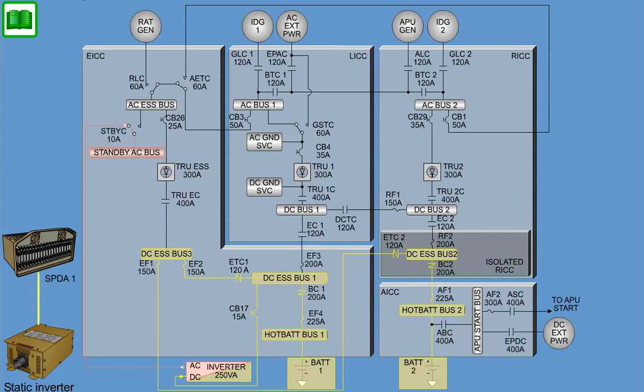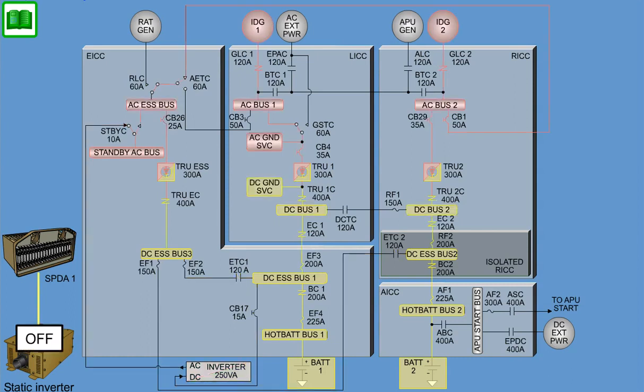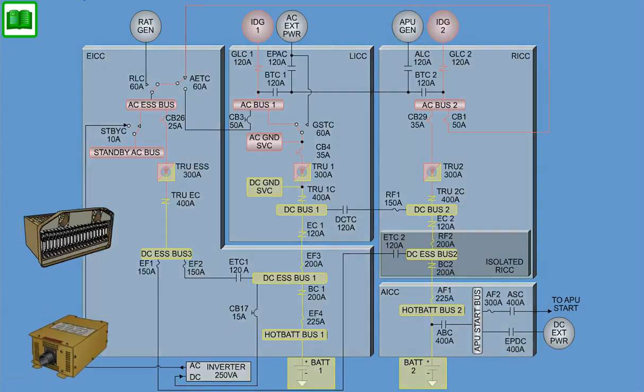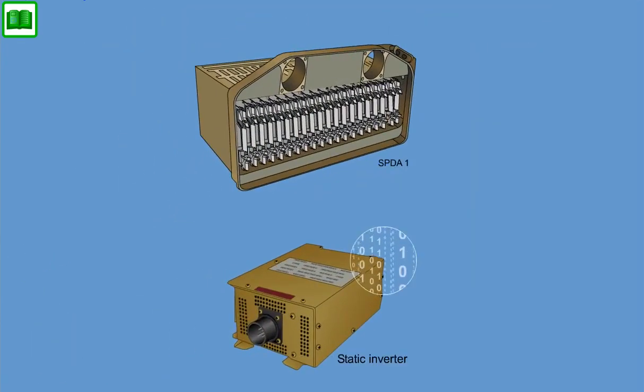SPDA1 will set the inverter to the off status during normal operation of the Electrical Power Generation and Distribution System, EPGDS. The SPDA1 will set the inverter to the on status in case only one main AC source is available, IDG1 or IDG2 or the APU generator. If the internal fault monitor of the inverter detects a problem, a discrete status signal would inform the SPDA1 to shut down the inverter.